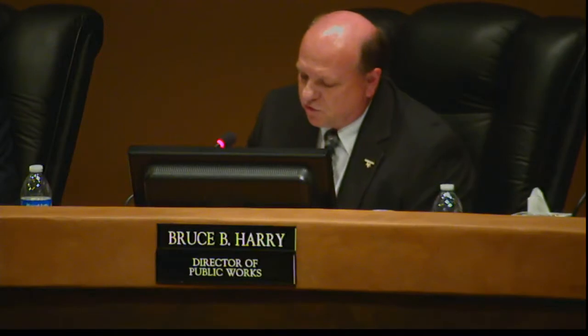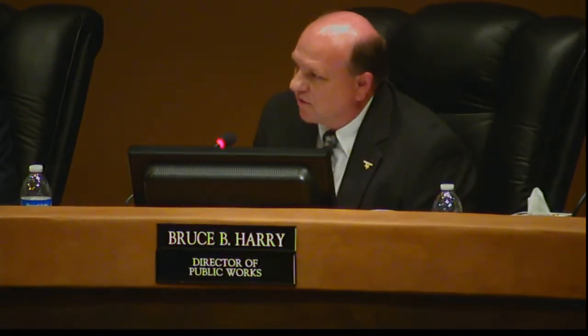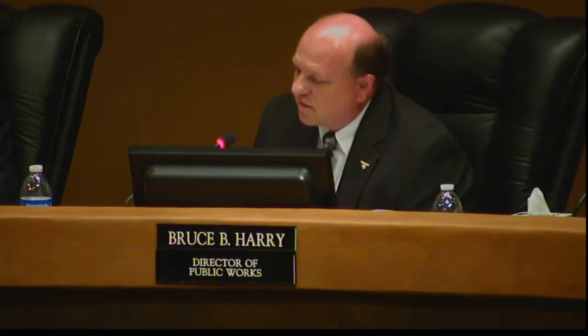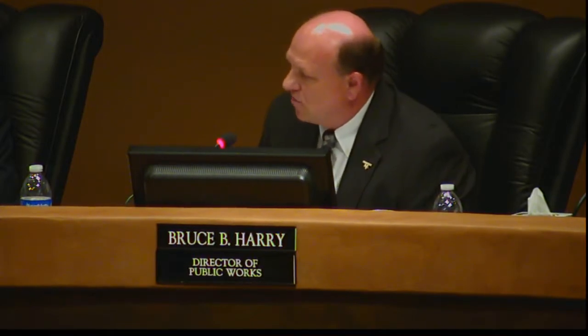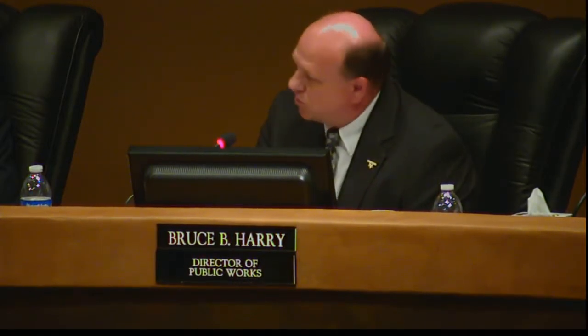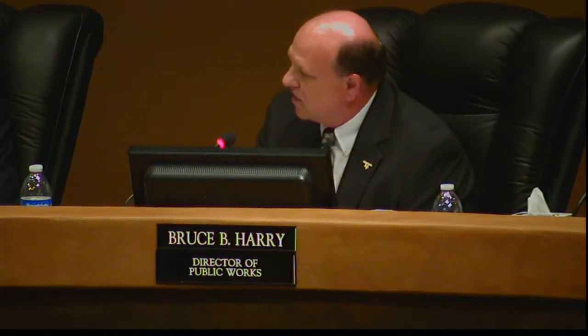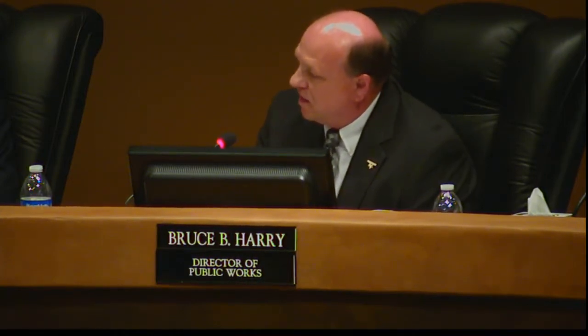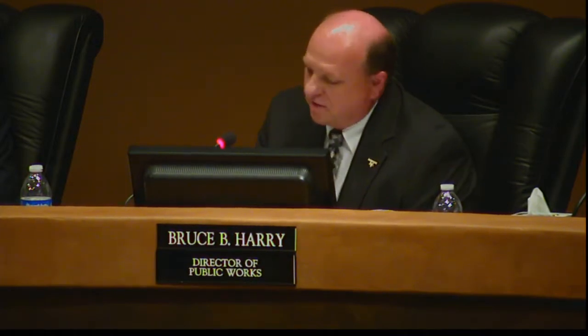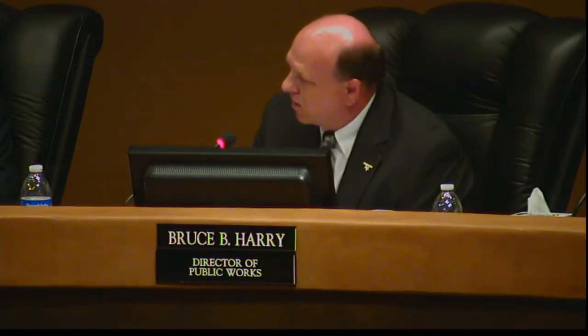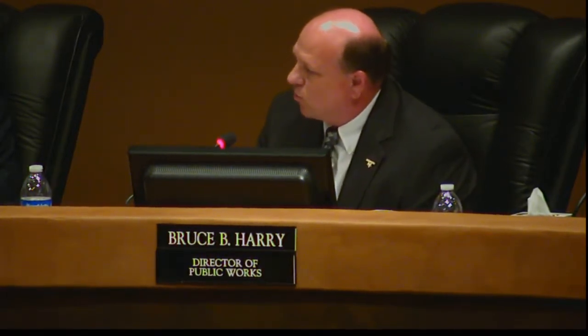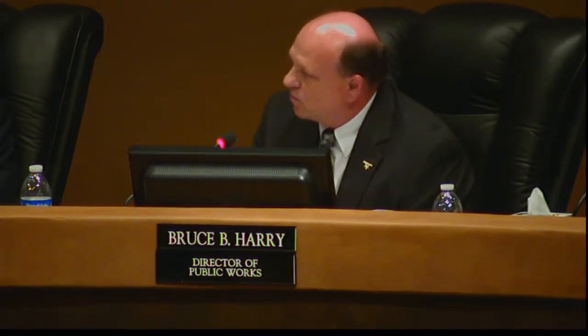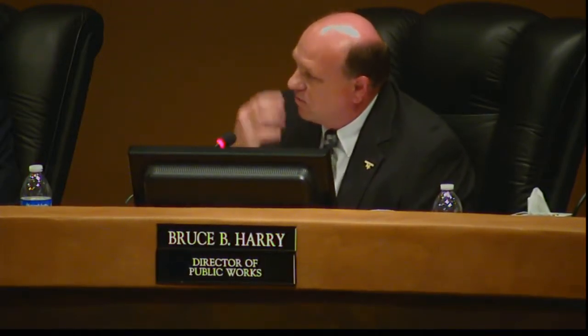Like I mentioned in the additional information I gave the council today, the maintenance contract is basically two components. You have a fixed component, preventative maintenance, which is what you see in their bid—fixed work done on a monthly basis, where they know what the services are and bid so much money to do that work. The second component is extra work, where they run into things—for example, a pump goes out, a fan coil doesn't work, you have chiller problems with the automation system, or you have to replace components of the HVAC system.